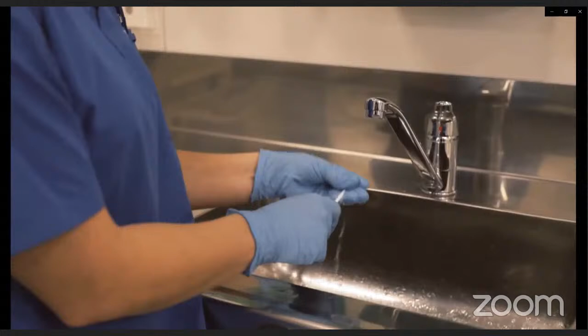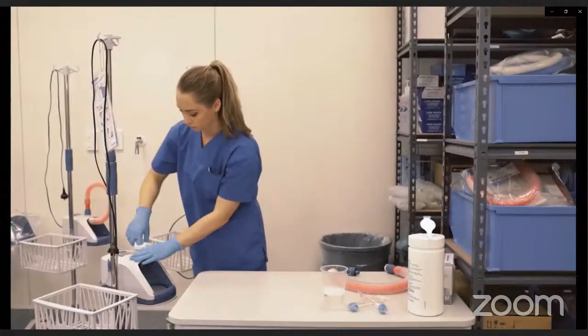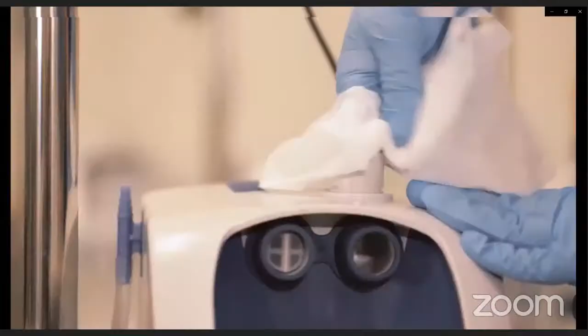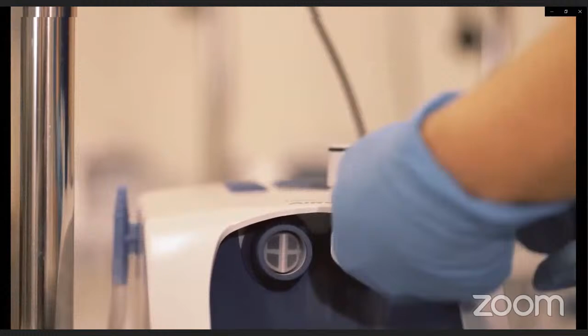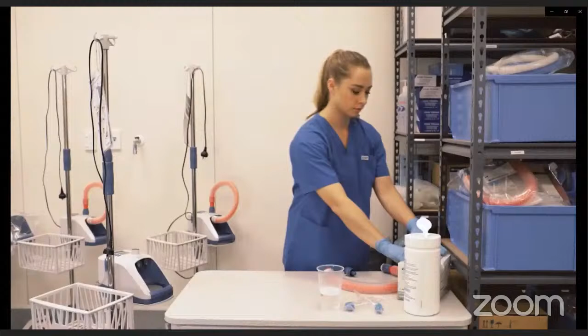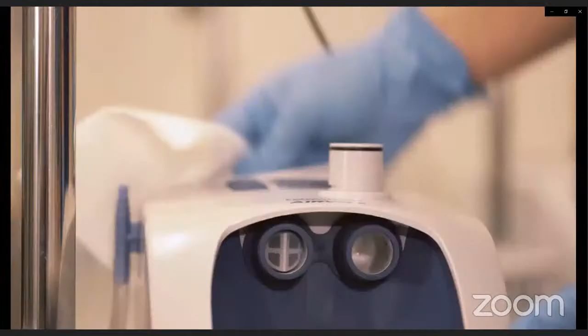Rinse the cleaning sponge stick under running water and, using the same rotation action, remove any residue from the outlet elbow. Discard the cleaning sponge stick. If using a disposable cloth, thoroughly clean the outlet elbow from both ends as far as possible, continuously rotating the cloth with your finger. Use an alcohol wipe or apply an alcohol solution to a clean, damp, disposable lint-free cloth to wipe the outside surfaces of the unit.